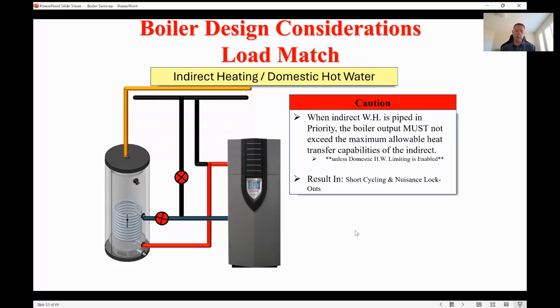So what's going to happen on a call for domestic? Well, this boiler, as smart as they are with these controls, they don't know what they're hooked up to. So this boiler is going to basically get a call for domestic. All right, it's going to turn that on, and it's going to be cold in there. So it's going to say, oh man, my set point's 180 degrees because I want to ramp that domestic tank up as hot as fast as I can. So it's going to turn on. It's going to see it's far away from set point. It's going to slam 2 million BTUs into there.